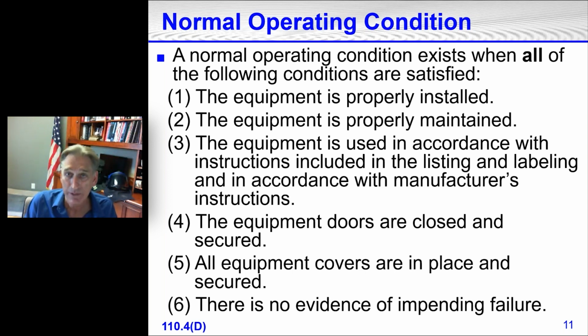That's not the door it's talking about. The door, like the door for a safety switch or a disconnect switch, or an industrial control panel, would have to be closed and secured. Not the outside door to the breaker box. By just opening that outside door, it exposes the breakers, but it does not expose any conductors, circuit or live parts of conductors or circuit parts.